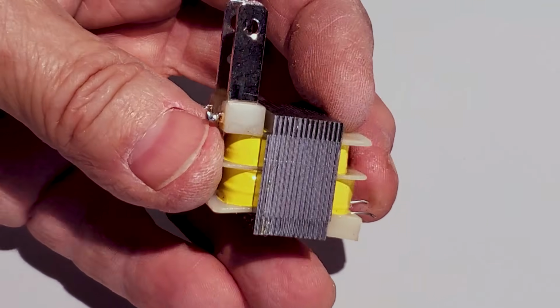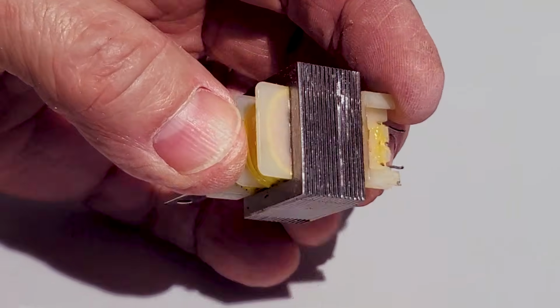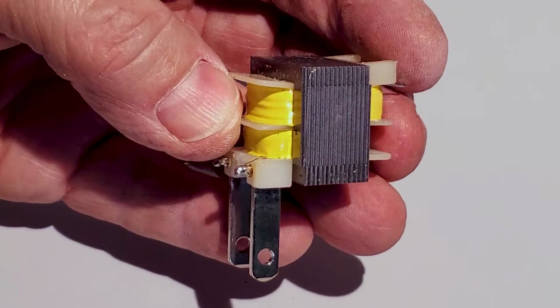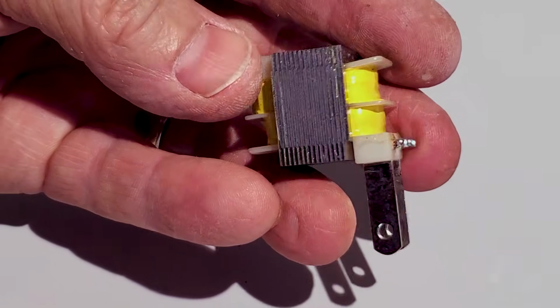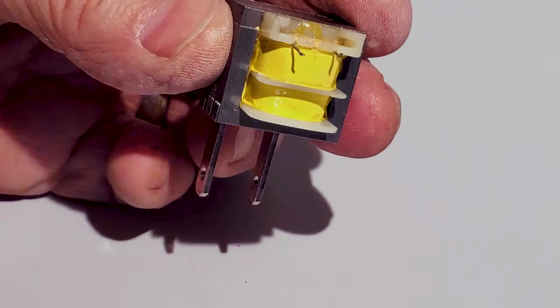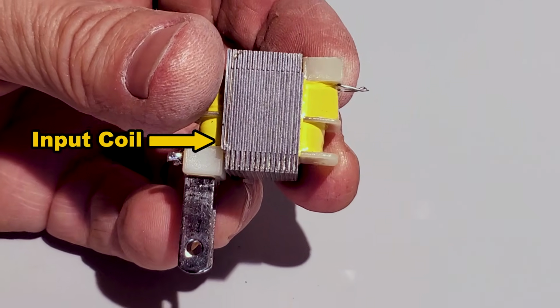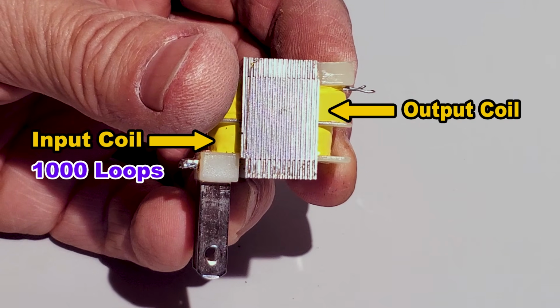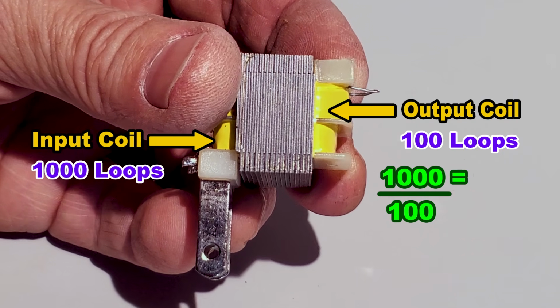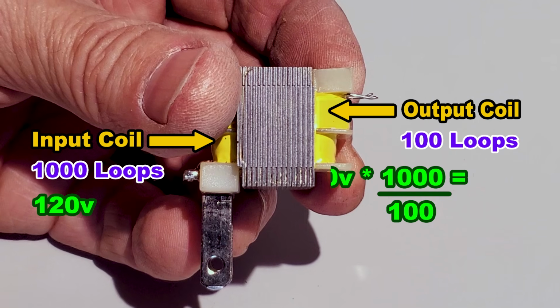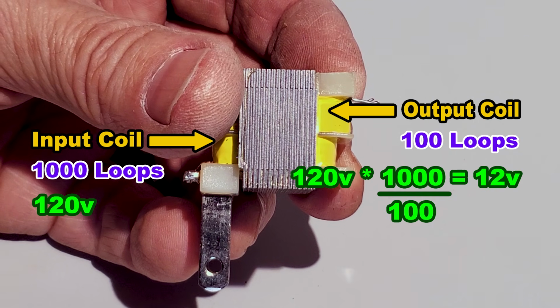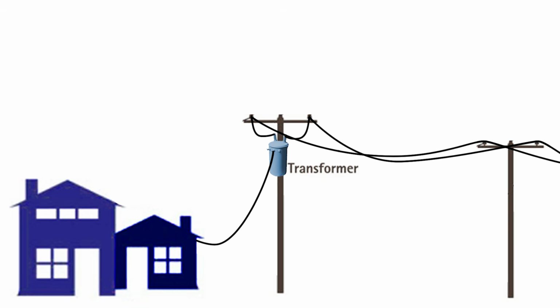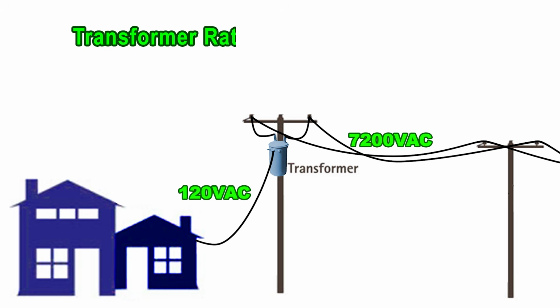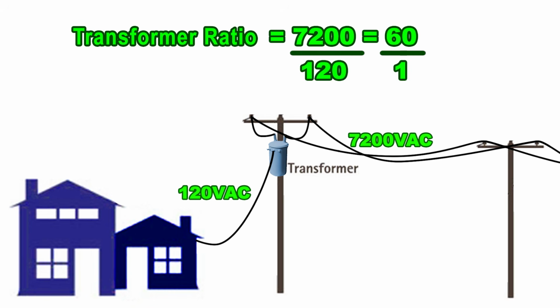The input AC voltage creates a magnetic field that induces an AC voltage on the output, and the ratio of coil windings determines the output voltage. For example, if the input coil has 1,000 loops and the output coil has 100 loops, the output voltage will be 1/10 the input, or 12 volts. So the residential transformer with 7200 volts input and 120 output has a transformer with a turns ratio of 60:1.